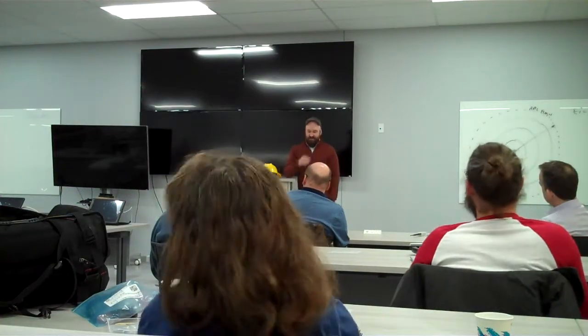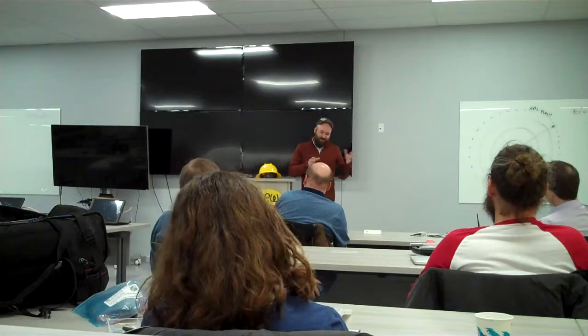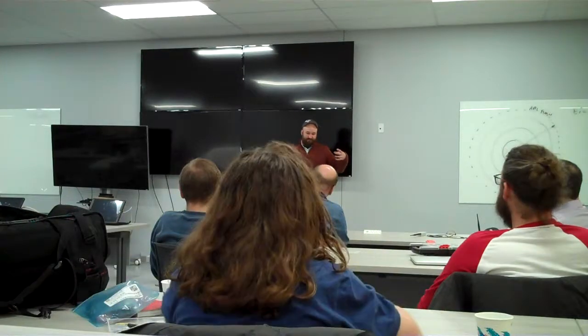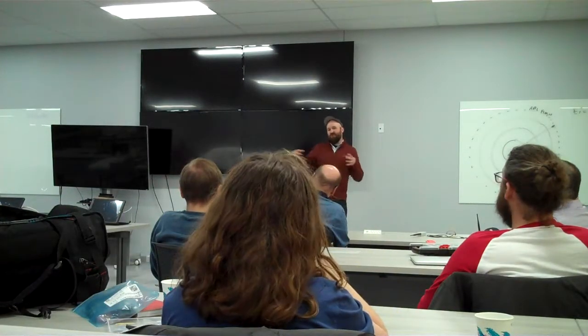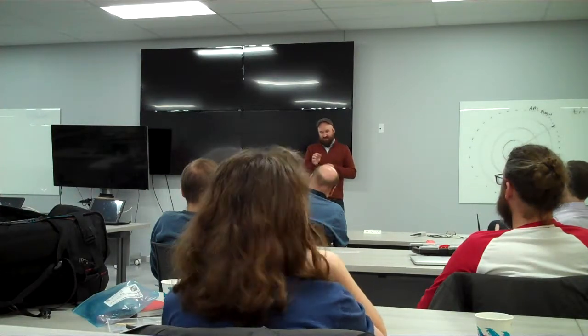Do your turbines float? I've heard of some of them that actually have some type of floating mechanism, like a liquid bed or something. Nope, ours don't have liquid beds. All the turbines that we have are pinned from one central location. So these out here, the Siemens SGT-800 made in Finspång, Sweden, came with, I'll back up a little bit. Because of the temperatures, both the steam turbine and the combustion turbines will grow quite a bit. Because you've got bearings on either end of the machine, that can cause alignment issues and vibration issues, so you need to control that growth.